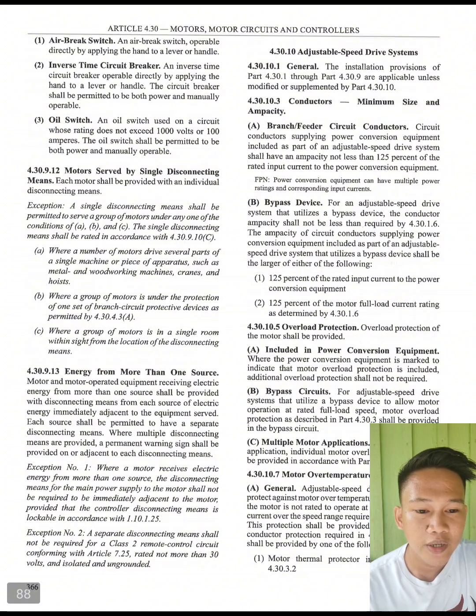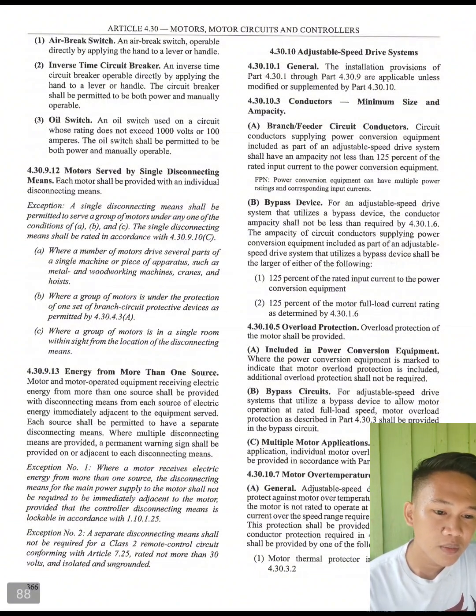Next is bypass device. For an adjustable speed drive system that utilizes a bypass device, the conductor ampacity shall not be less than required by 4.30.1.6. The ampacity of circuit conductors supplying power conversion equipment included as part of an adjustable speed drive system that utilizes a bypass device shall be the larger of either of the following. First, 125% of the rated input current to the power conversion equipment. Second, 125% of the motor full load current rating as determined by 4.30.1.6.